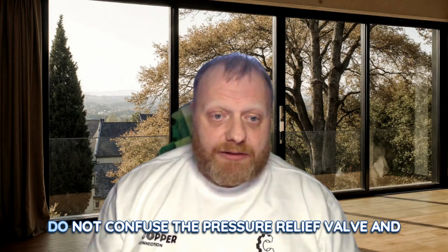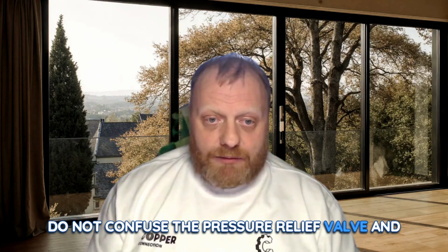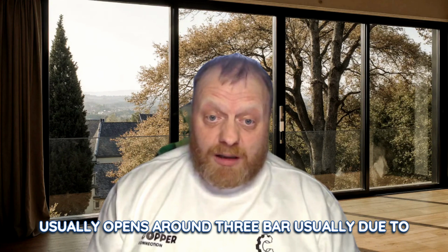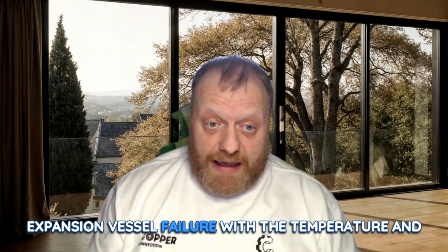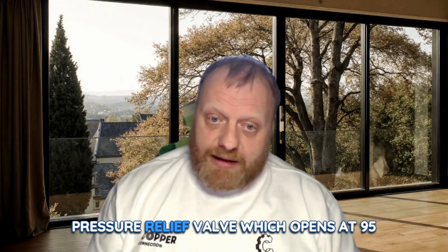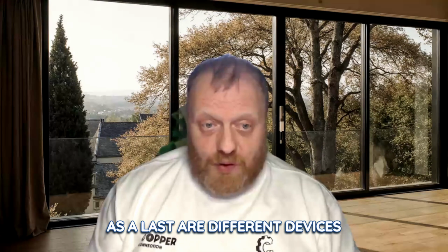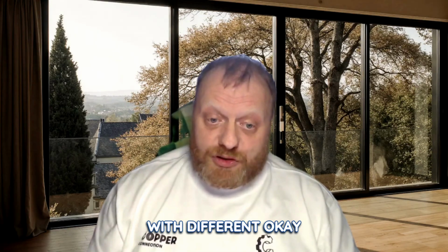A common mistake: do not confuse the pressure relief valve, that usually opens around 3 bar, usually due to expansion vessel failure, with the temperature and pressure relief valve, which opens at 95 degrees or 5 bar as a last resort. They are different devices with different functions.